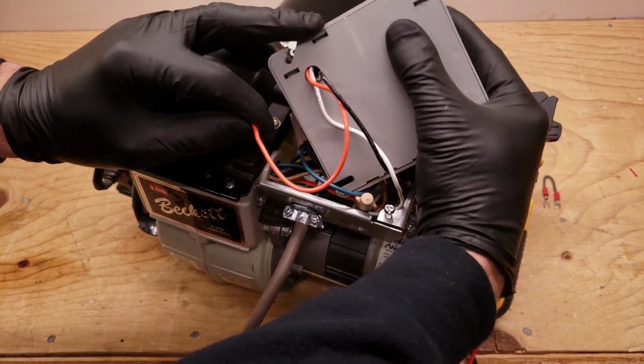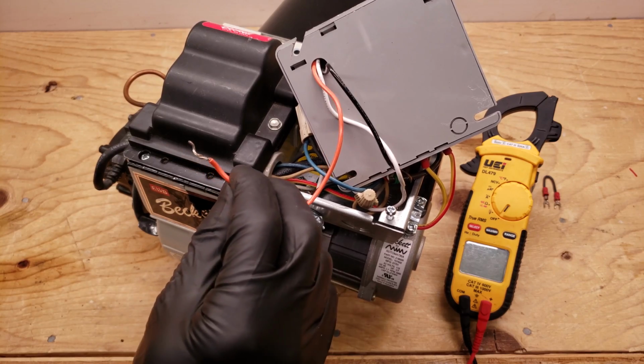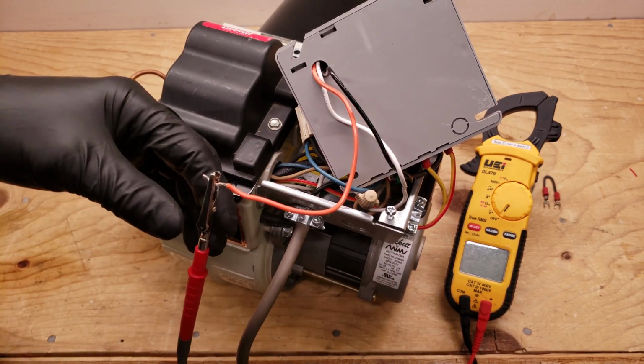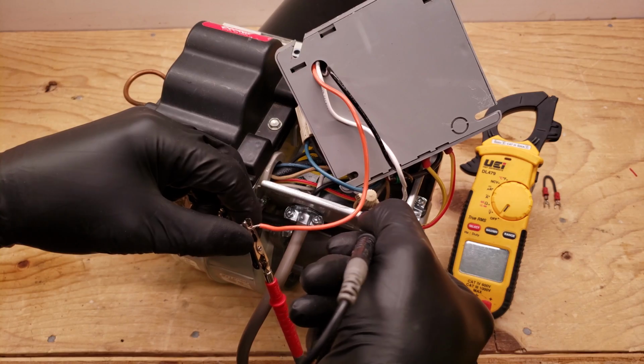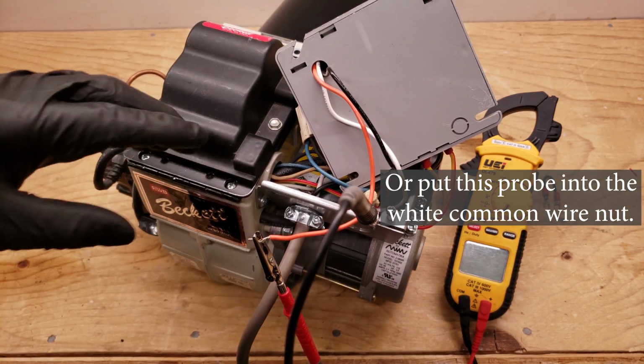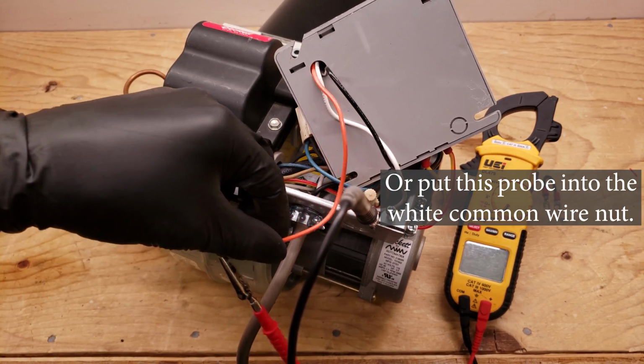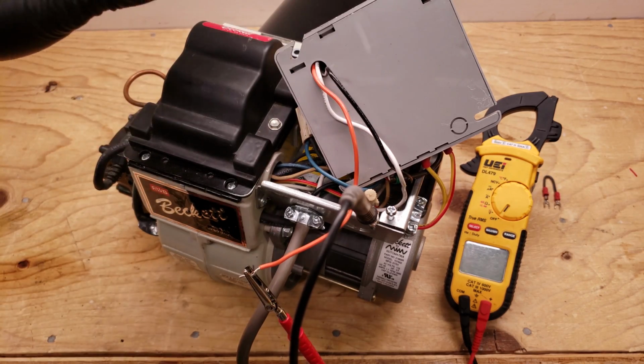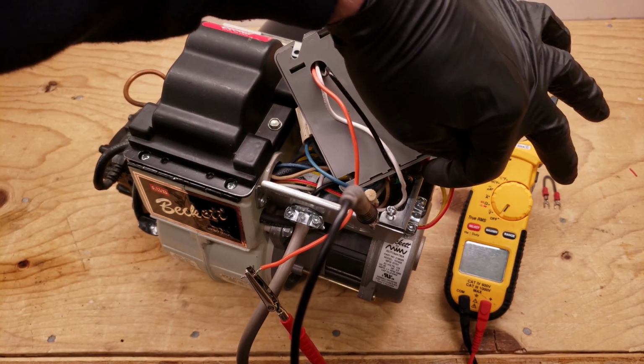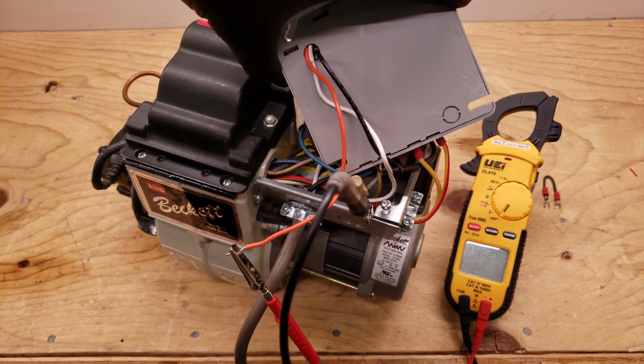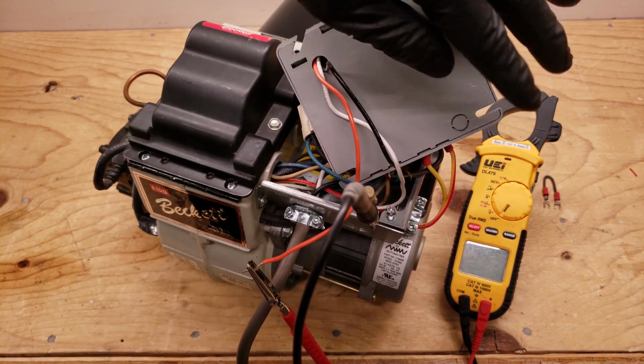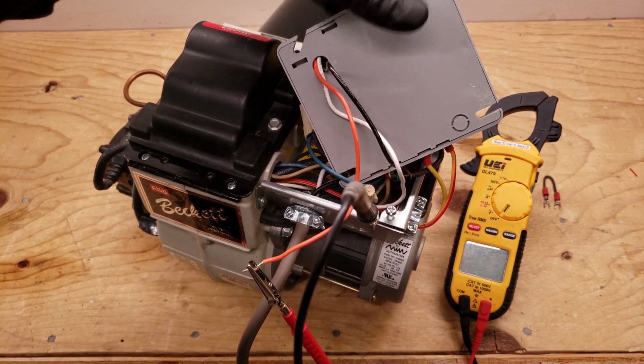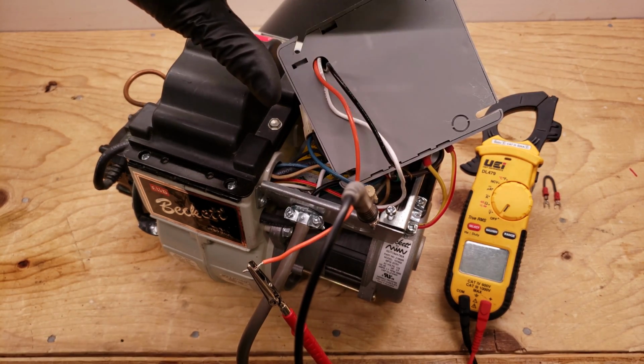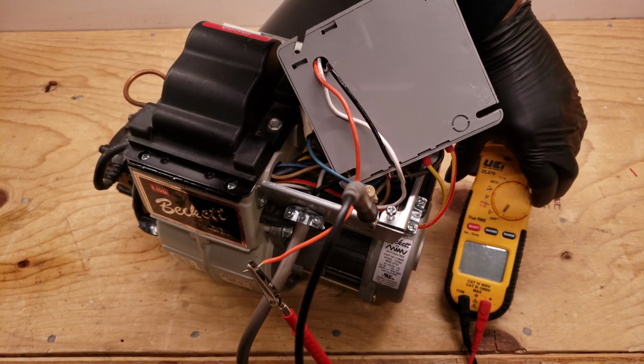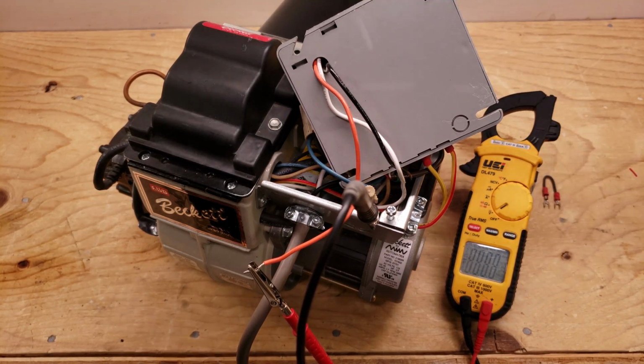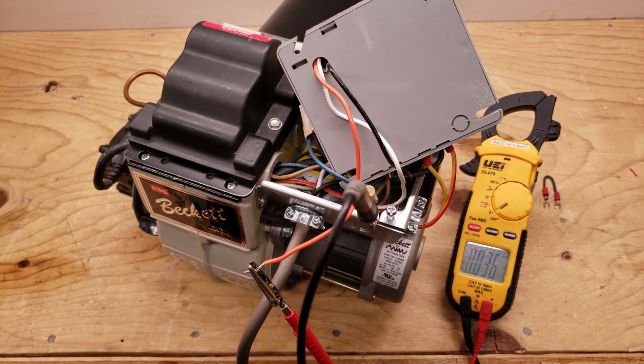Got to position this, so there we go. We'll put our alligator clip on there, and then we're just going to read on the ground for now. And we're going to be able to read 120 volts coming out if there's no problem. So we want to make sure that there's no terminals that are touching the ground frame or anything like that. And right now there is none. But you can hold this up in the air, push to the side. But I'm just kind of setting this here for the sake of the camera and so that you can see the multimeter. Now I'm going to go ahead and plug this in.